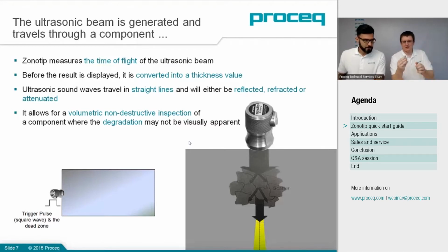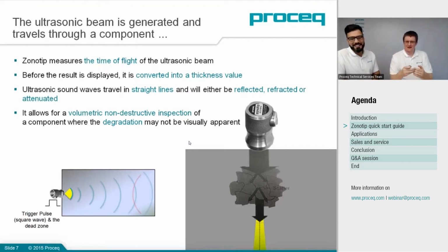Here, for example, is our single crystal probe, and what it contains inside is a piezoelectric crystal. The Zonotip sends a pulse to this, a voltage, a square wave, as is shown there. That expands the crystal when it's applied, and when it's removed, it contracts back down to its normal dimensions. If you do this repeatedly, then you will get an ultrasonic beam generated.